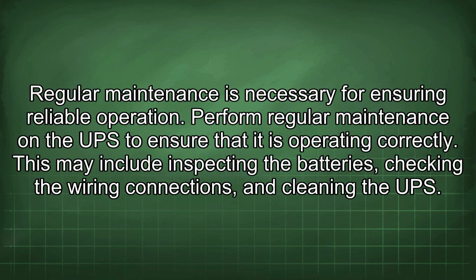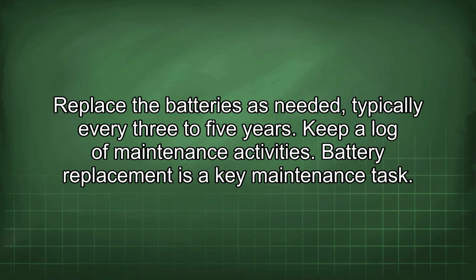Regular maintenance is necessary for ensuring reliable operation. Perform regular maintenance on the UPS to ensure that it is operating correctly. This may include inspecting the batteries, checking the wiring connections, and cleaning the UPS. Replace the batteries as needed, typically every 3 to 5 years. Keep a log of maintenance activities.